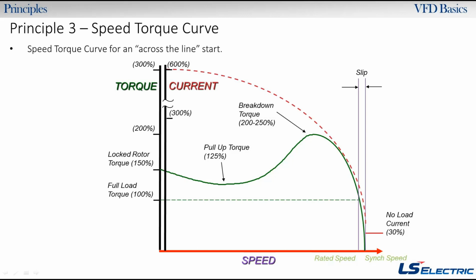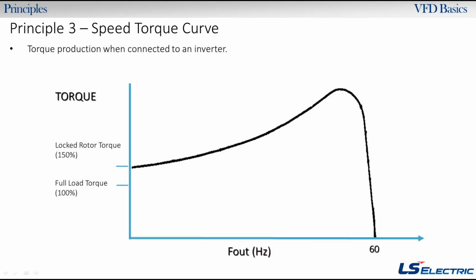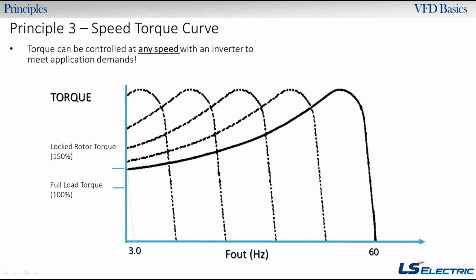Okay? So this is just what it would look like running across the line. No speed control, right? Now, if we were to connect that same motor to an inverter, a VFD, we could move that speed torque curve wherever we want. Okay? So we could have any speed we want within reason, and any torque we need, at a low speed, a high speed, a middle speed. Okay? So this is great because it gives us a little bit more dynamics for different applications.